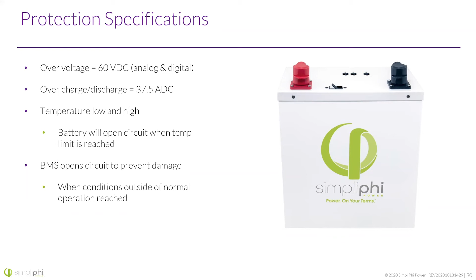With the Phi battery, the sizing guideline really needs to be followed, or you're leaving yourself open for possible damage not covered under warranty. With the AmpliPHI, if it's hooked up to the Sol-Ark, it will tell the Sol-Ark exactly how many batteries are in its bank and will ramp down that discharge rate. The battery itself ensures no over discharge happens, so we don't need to follow that same rule as with the Phi battery. We could have two AmpliPHI batteries on a 12 kilowatt Sol-Ark, and as long as it's hooked up correctly with the communications cables, it will communicate that it cannot overcharge or discharge beyond a certain point.